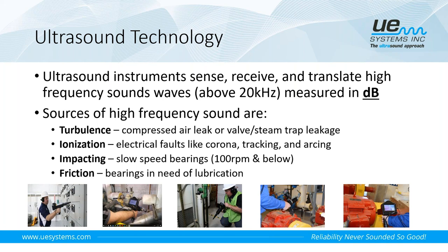And we're listening for these sounds above 20 kilohertz. So most of our instruments, including the Ultraprobe 401, will have frequency tuning capability, so we can tune it according to what the application is. In our case here today, talking about bearing lubrication, the Ultraprobe 401 digital grease caddy will come set from the factory at a frequency setting of 30 kilohertz, and that is the optimal frequency setting for bearing inspection. So it'll come right out of the box, already preset for the optimal frequency for bearing condition monitoring.